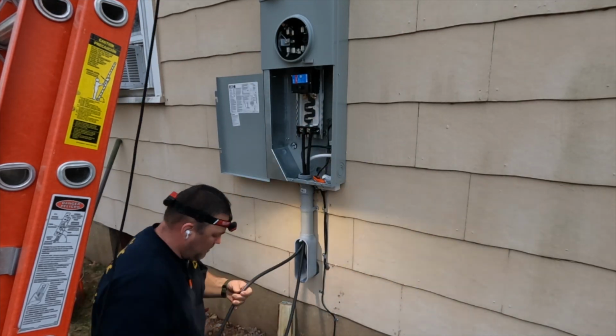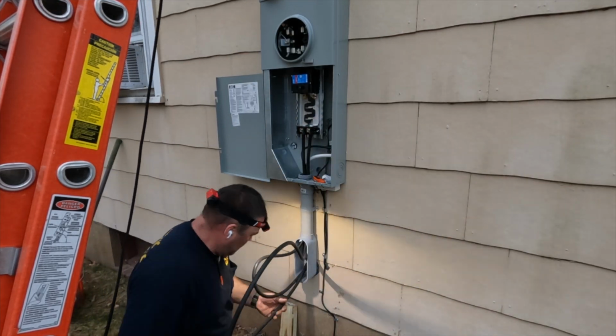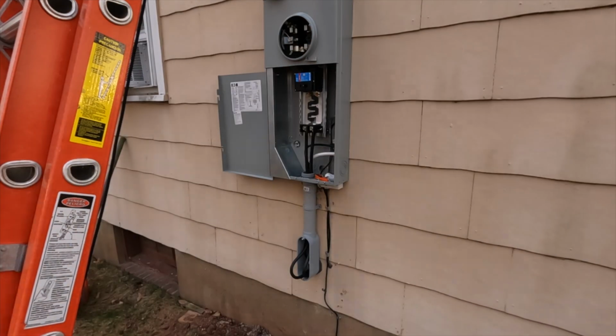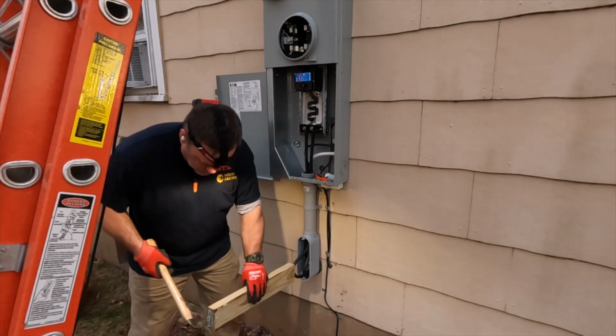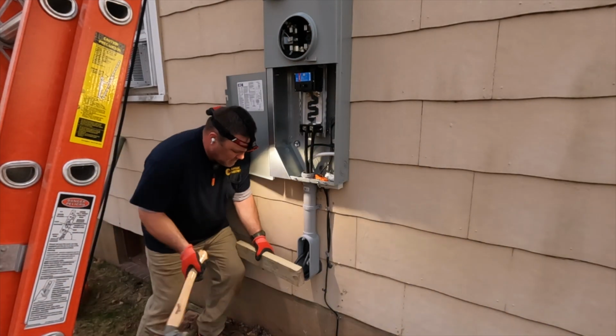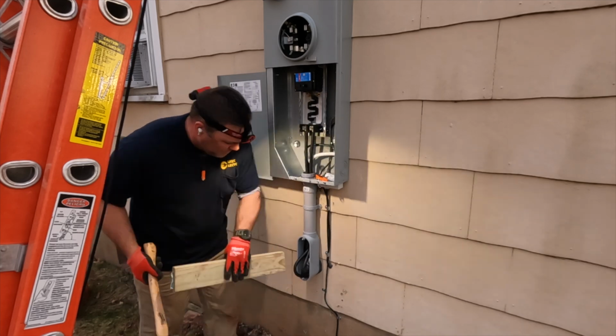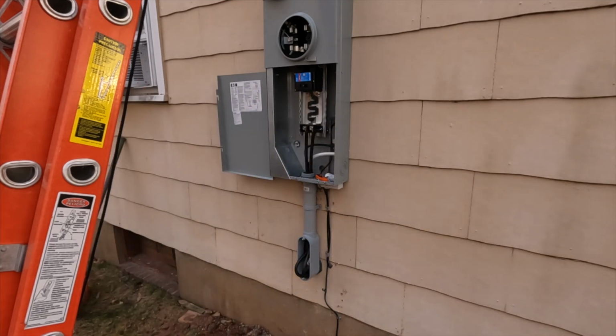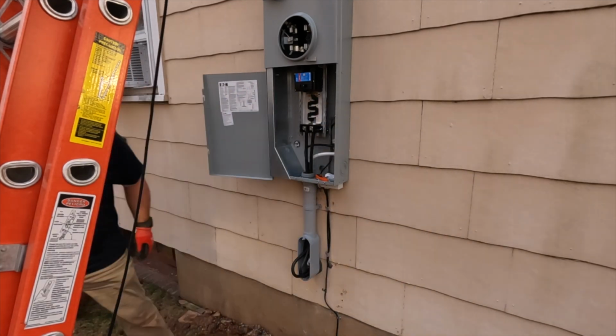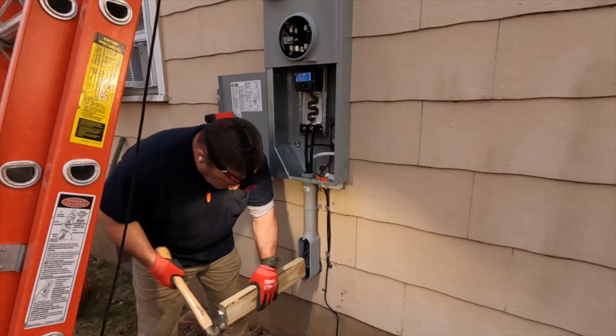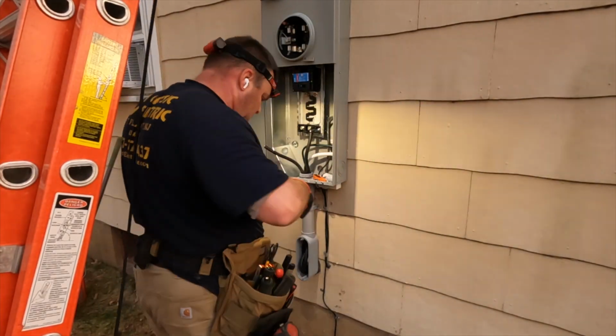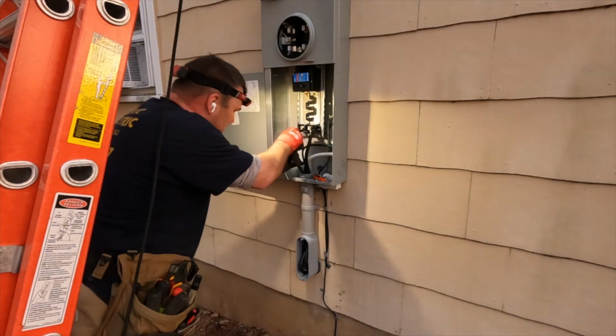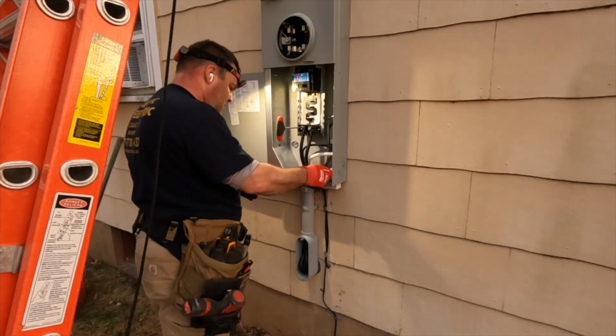You've seen me using it before, and I use that 2x4 right there to actually help the conductors go into the panel. As you can see there, I'll use it to persuade the conductors into the LB. We don't want to damage the insulation, which is why I'm using that block of wood. And finally I get them inside, and so now I'm going to terminate them to the terminals here. This is what we call a feed through panel.